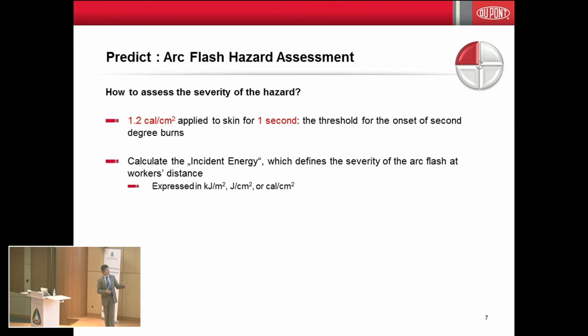This simulation allows you to calculate what is called the incident energy. This is basically an element defining the amount of energy that a given system or installation could generate in case an electrical arc was generated. This amount of energy is expressed in kilojoules per square meter, which is the ISO international standard unit, but most often people talk about calories per square centimeter.